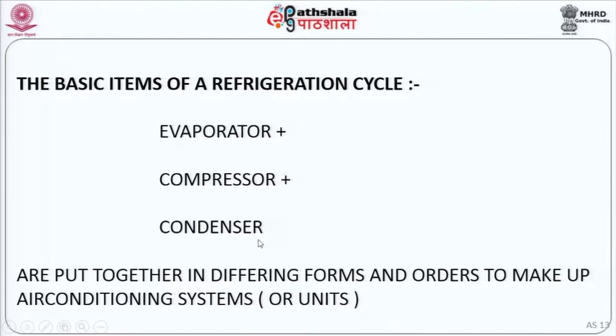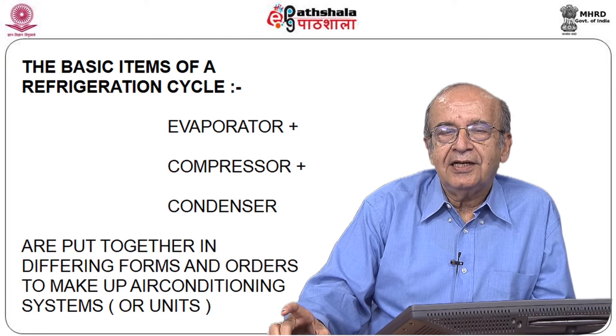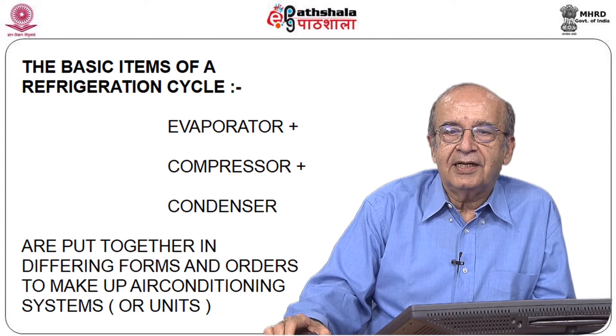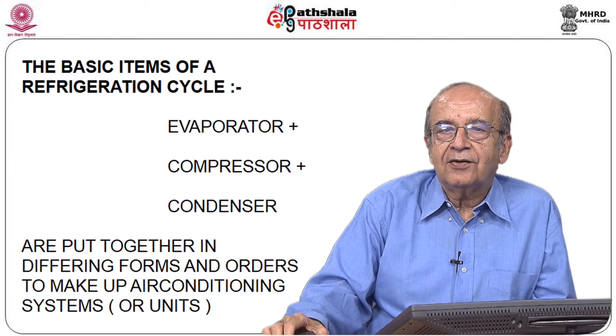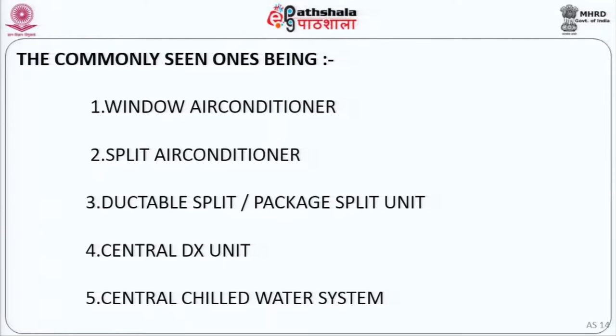All these systems have these three components as an essential requirement: the evaporator, the condenser, and the compressor which links the two. How they are put together forms the system. The ones commonly seen using the vapor compression cycle are: a window air conditioner, a split air conditioner, a ductable split which is a larger version, and the larger version of the three devices put together called a central DX unit. This unit has a handicap that it is a single-zone device, and for multi-zone applications it gives way to a central chilled water system.